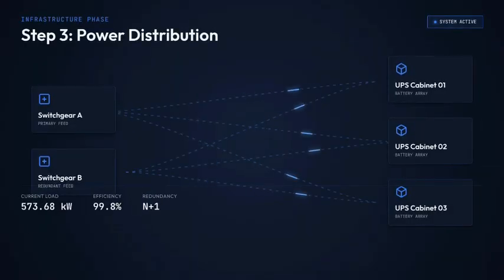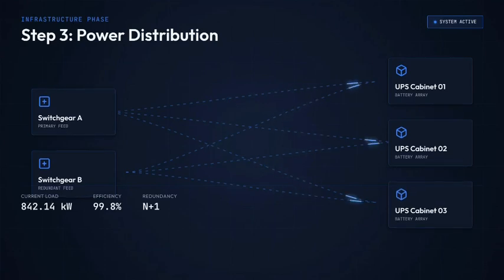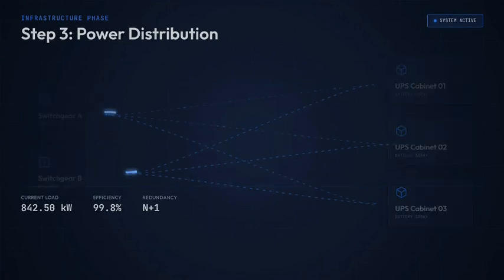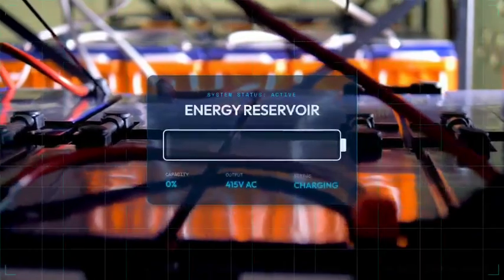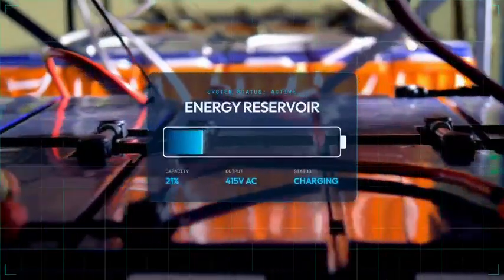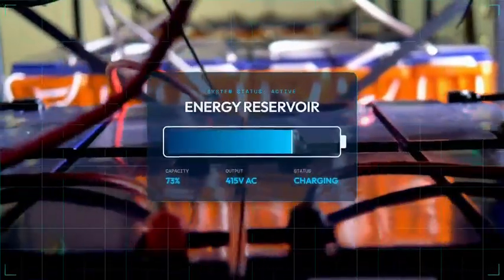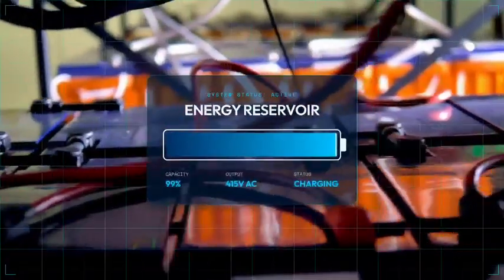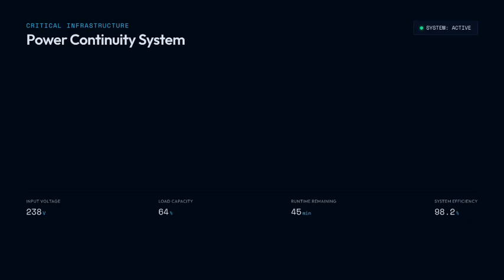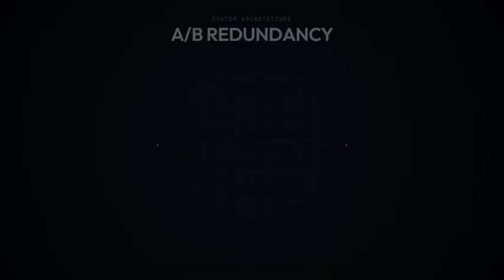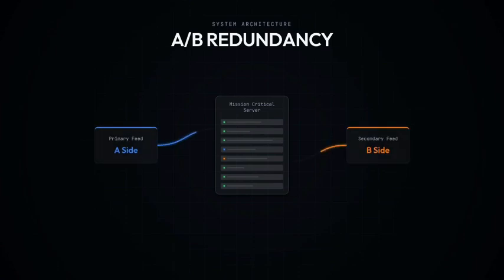Step 3, clean power to the racks. From the switchgear, electricity flows through UPS systems, uninterruptible power supplies, and out through PDUs, the power distribution units feeding each rack. Here's the clever bit. The UPS sits in the middle holding a reservoir of stored energy. So if the grid so much as flickers, it fills the gap instantly before a single server notices. And critical gear is fed by two independent paths, an A side and a B side, so no single failure can ever pull the plug.